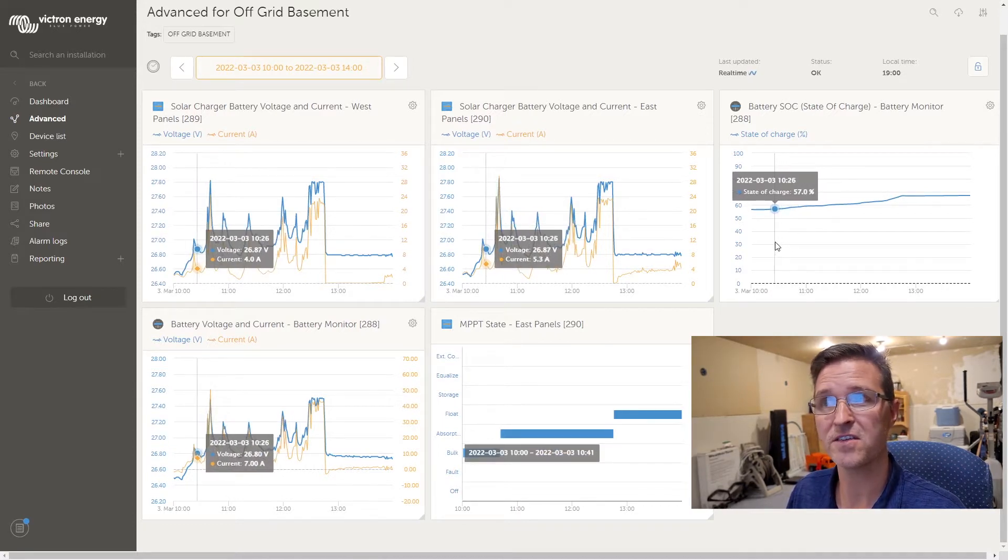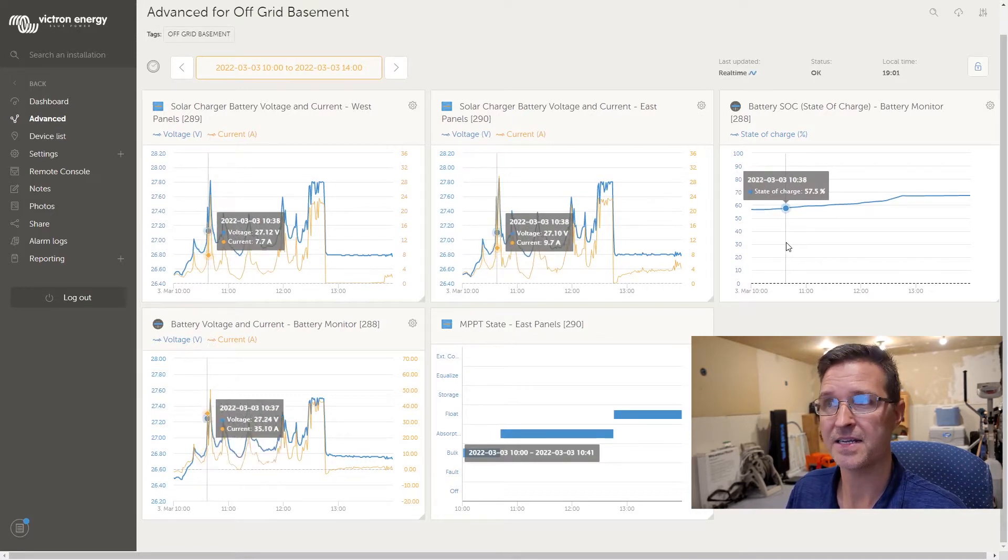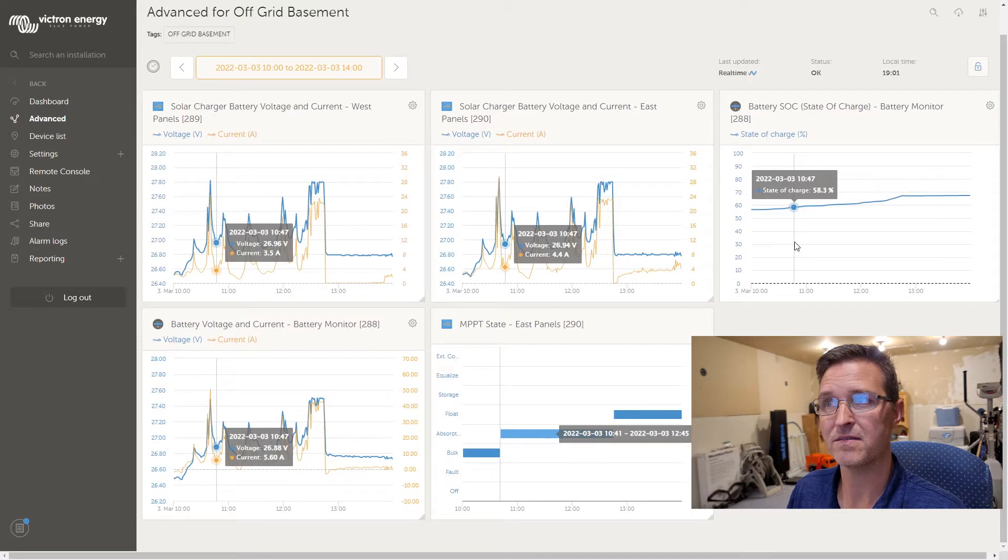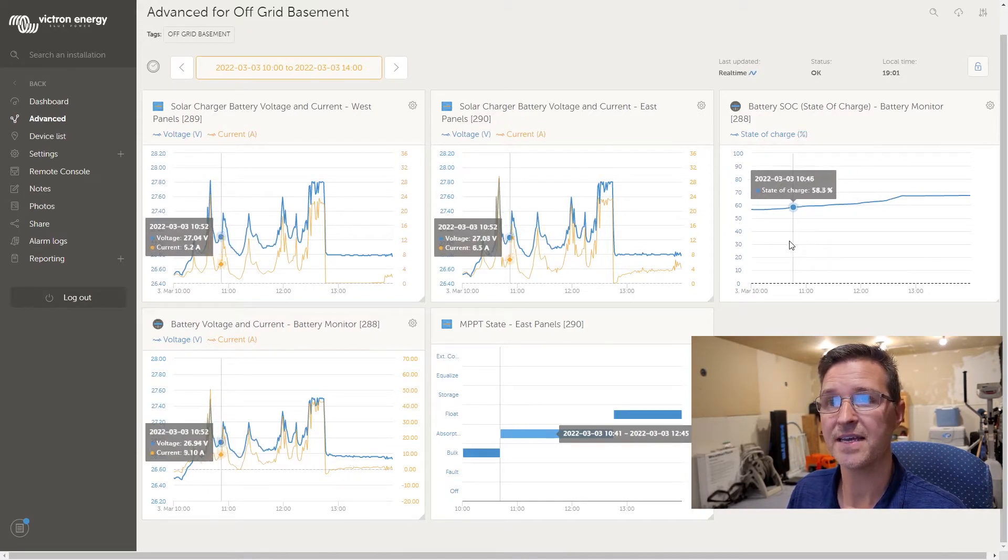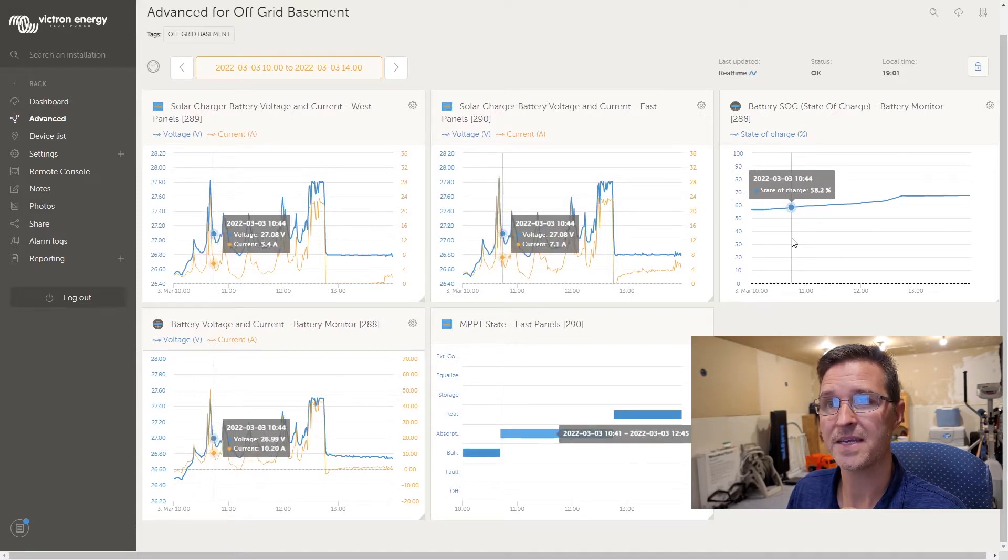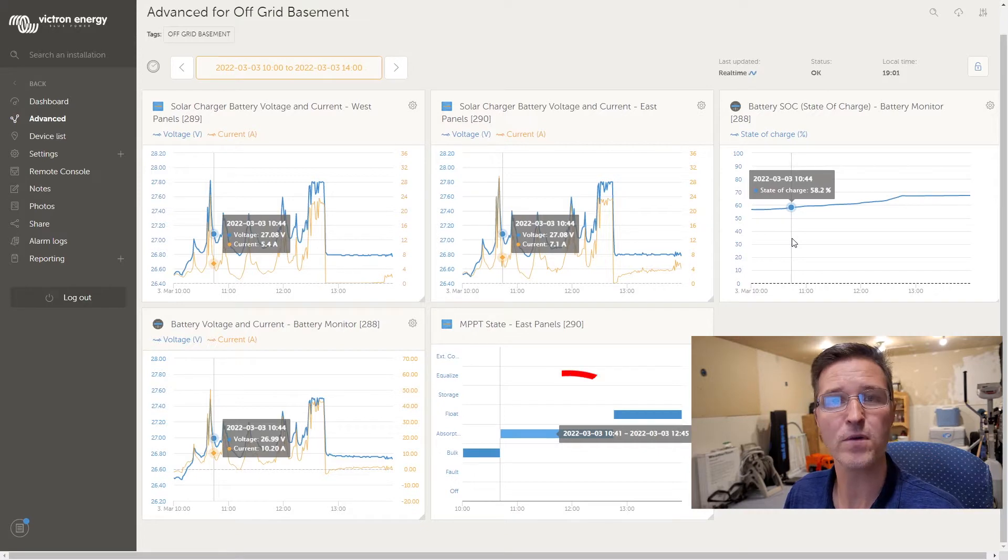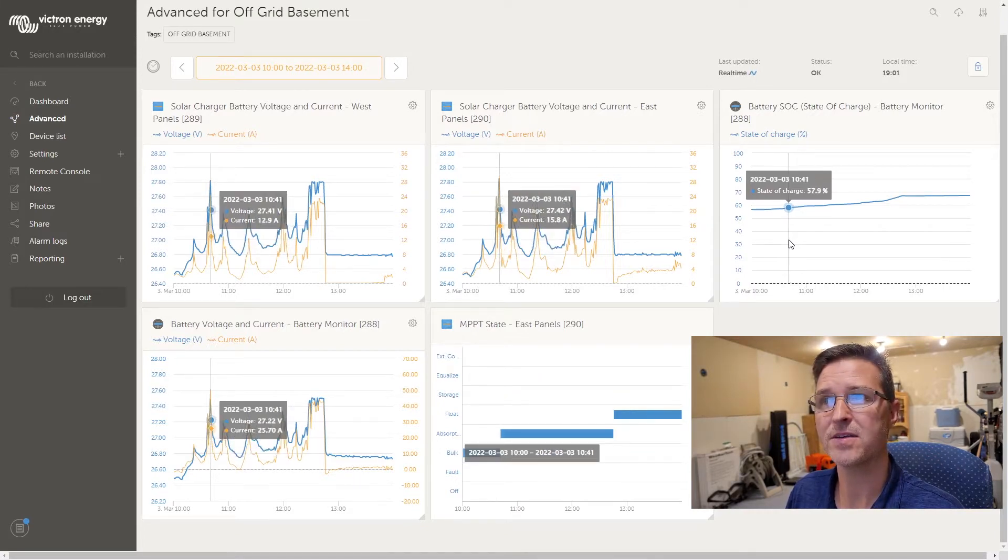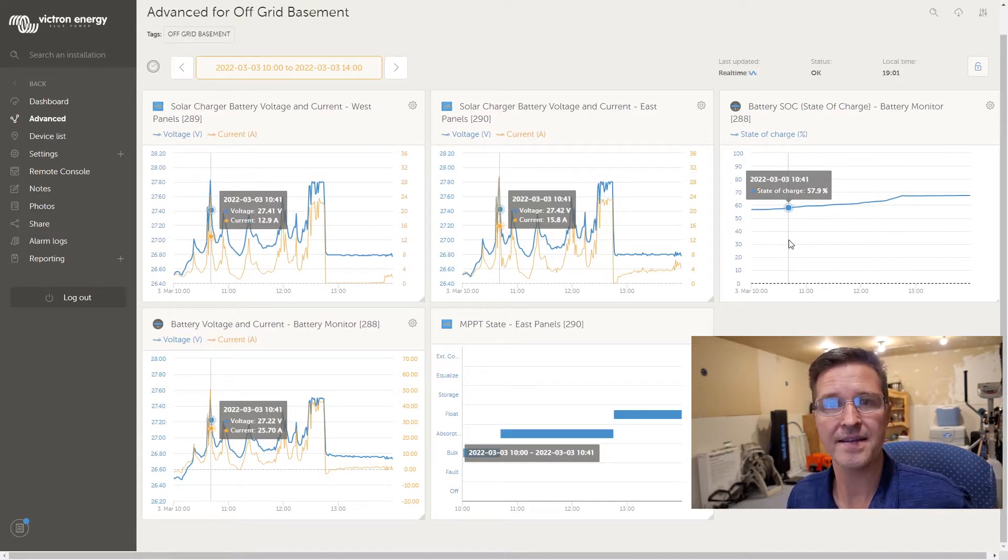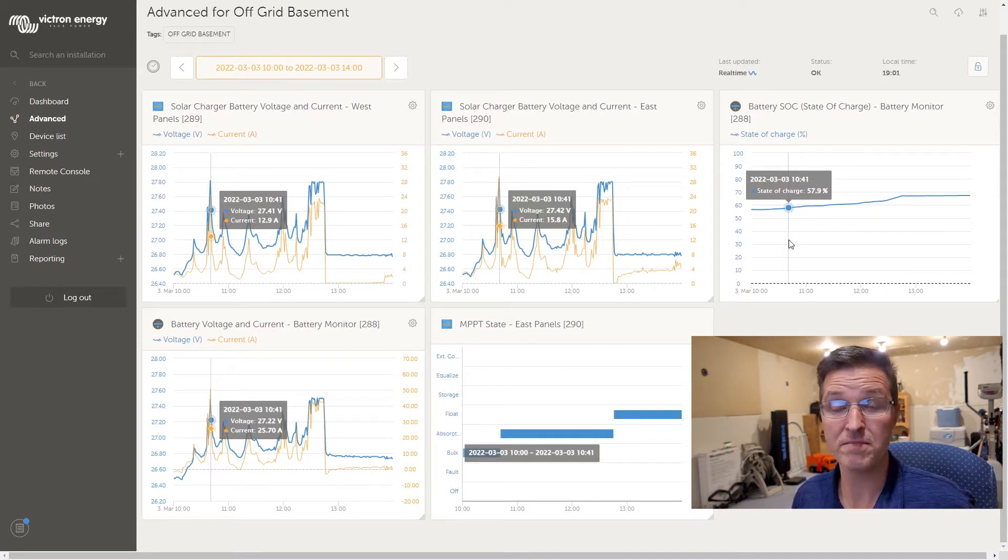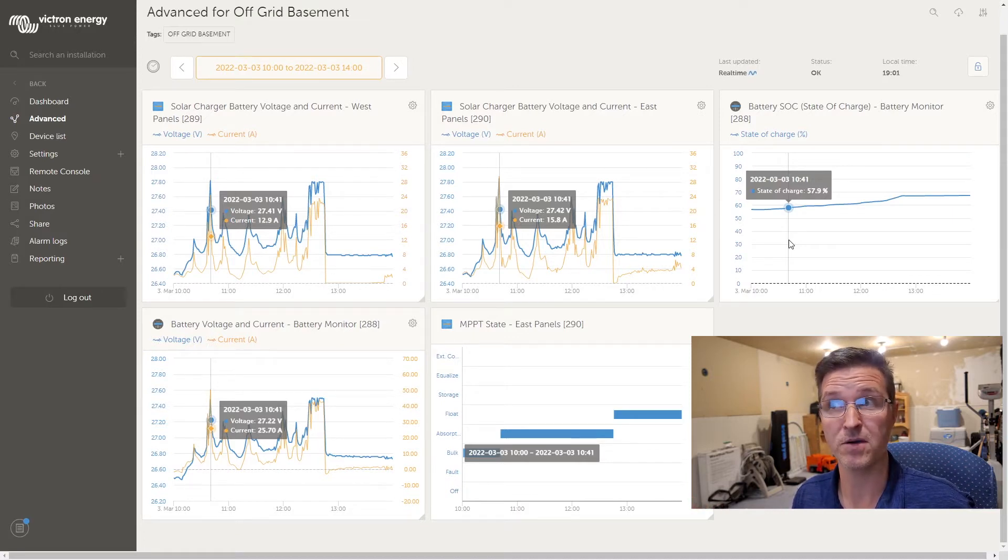It was in bulk mode and as you can see over on the right hand side here we're at 58 percent and then it goes into absorption mode at 10:41 AM. At 10:41 AM you can see that I'm only at a 57.9 state of charge, and how I have it set, my state of charge should be well above 80 before it goes into absorption mode.